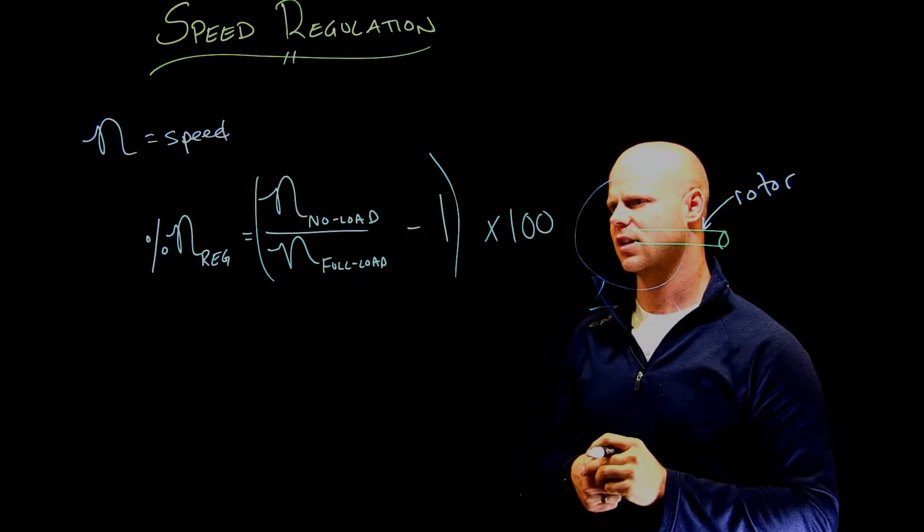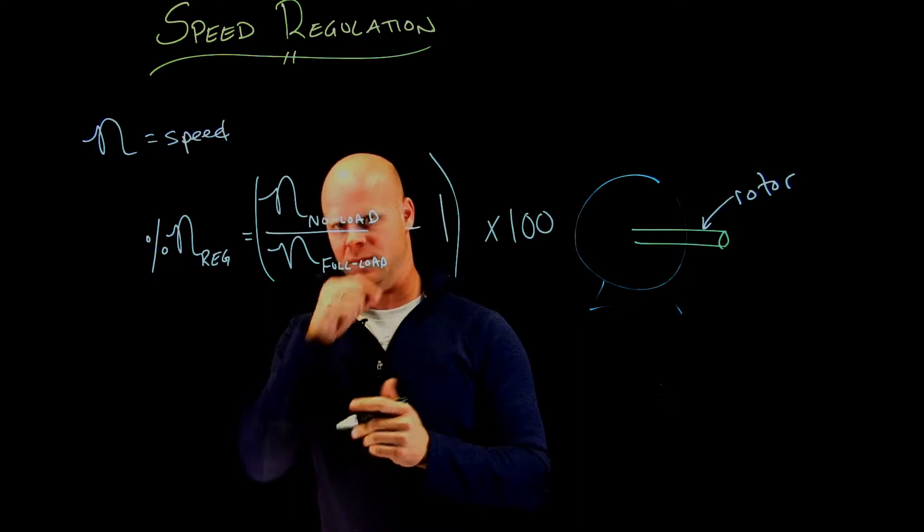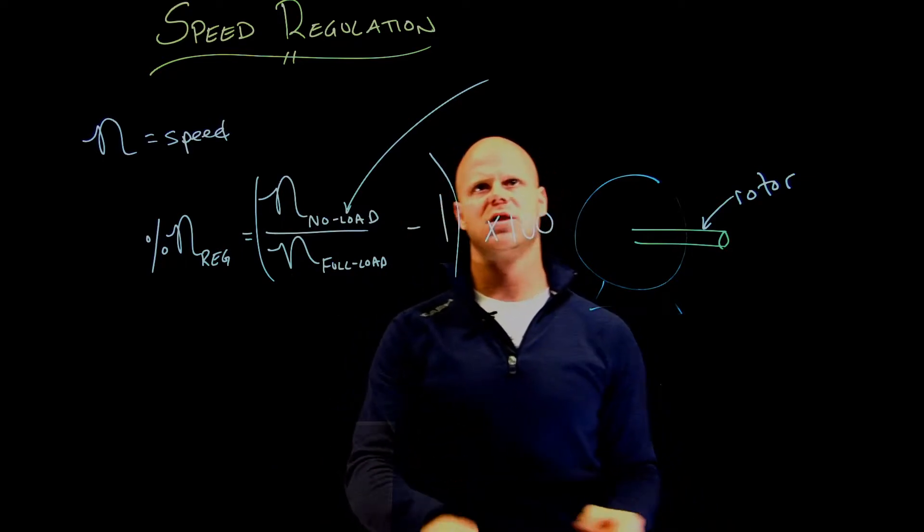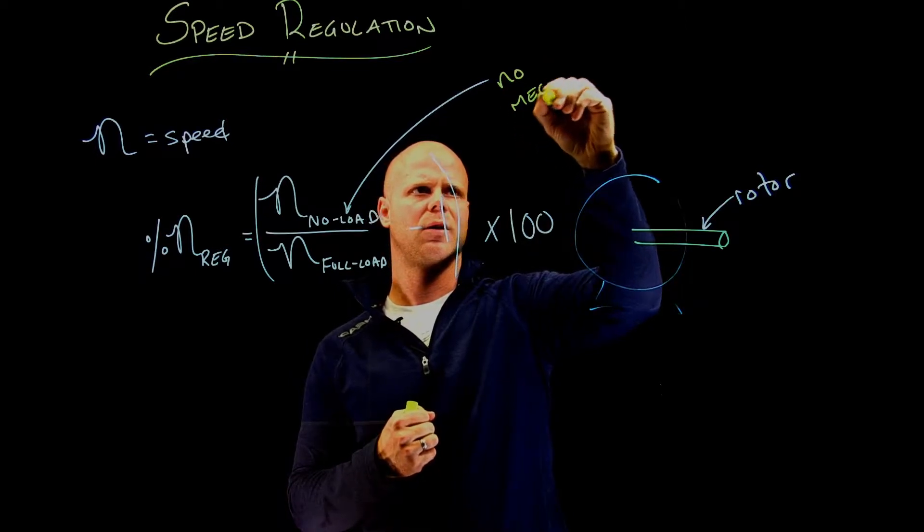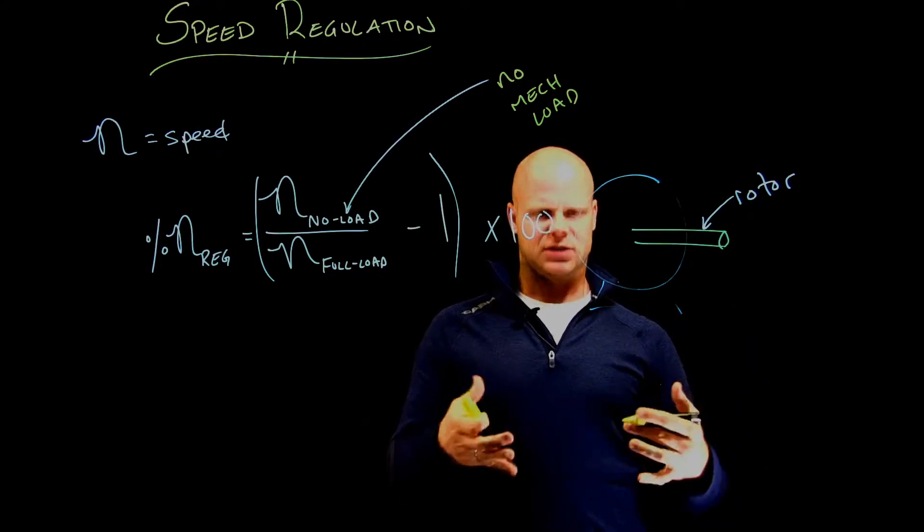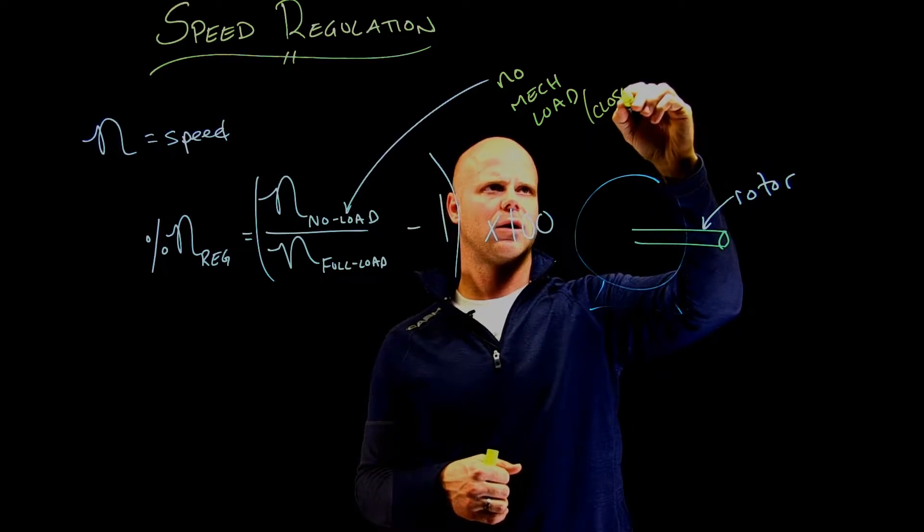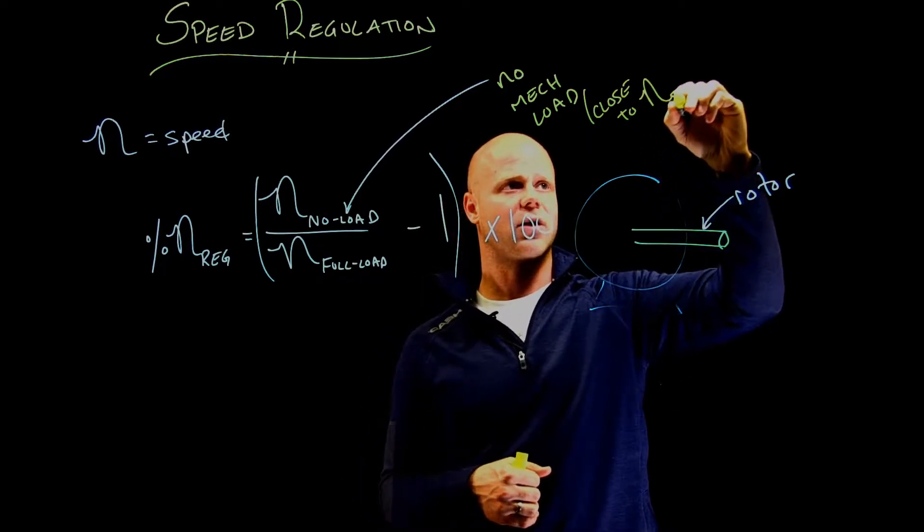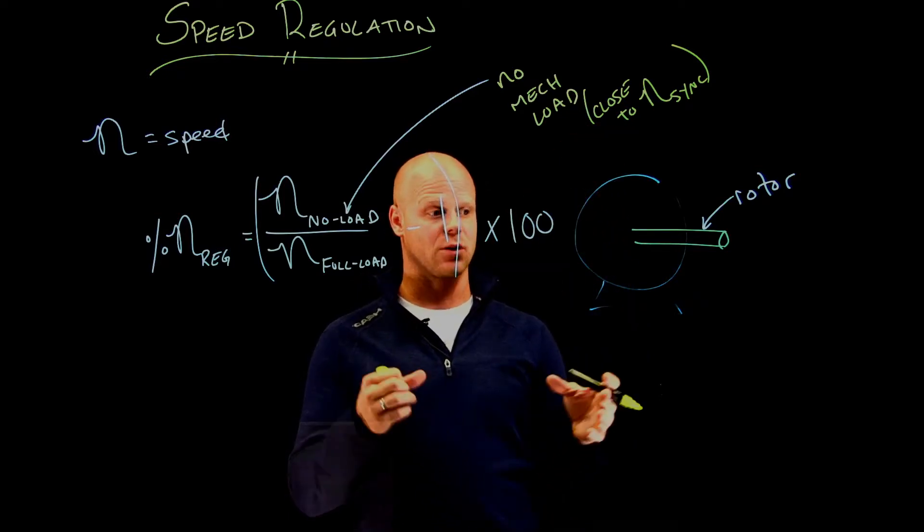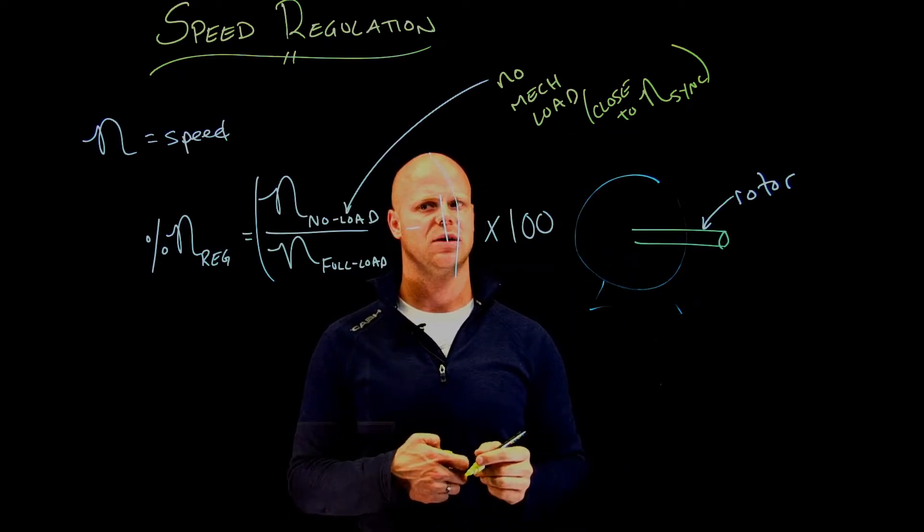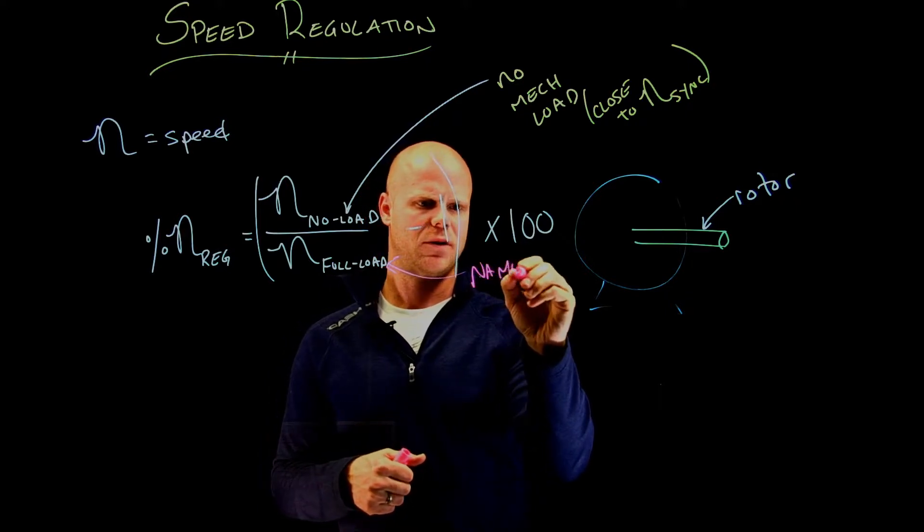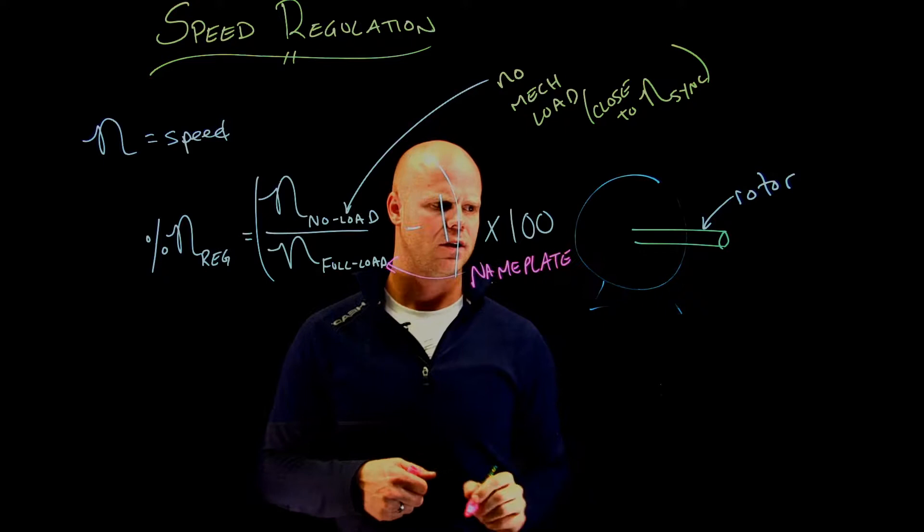What's really important to remember is the principles of my no-load speed. No-load speed means no mechanical load, so that rotor right now is just freewheeling. This is always going to be really close to my synchronous speed, which we'll talk about later. My full-load speed, this is a nameplate value—that's a nameplate piece of information.